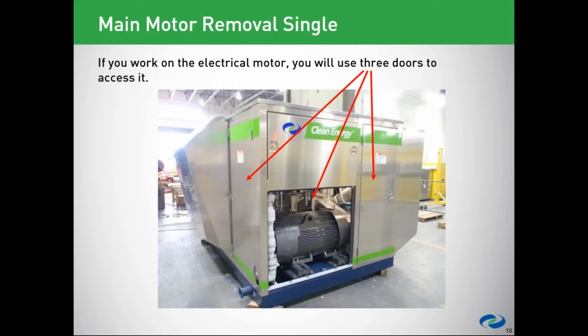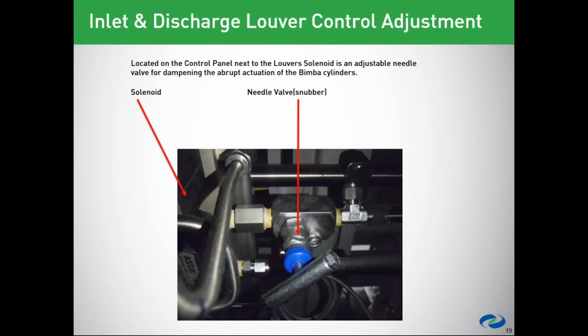Okay, the inlet and discharge louver control mechanism. There's an adjustment valve to control the speed of the louver opening and closing, so it doesn't slam and make a lot of noise and possibly cause breakage or whatever. So they put a variable snubber, so to speak, in here. The needle valve is acting as a snubber on this, and you can control the speed.